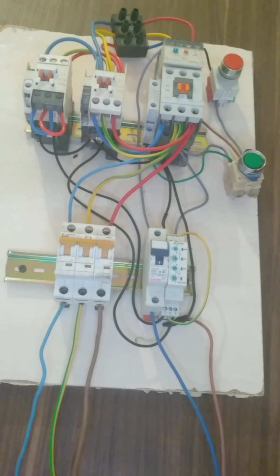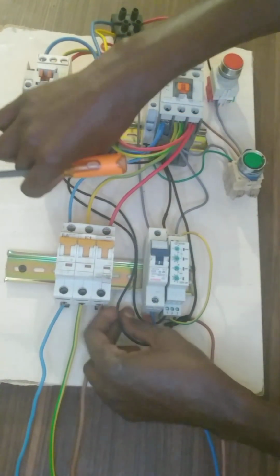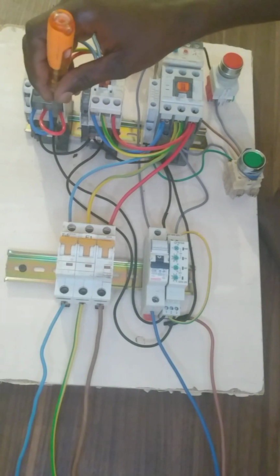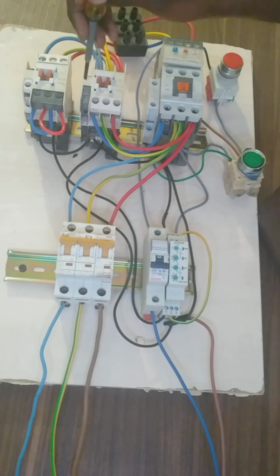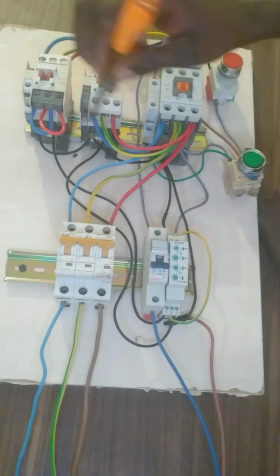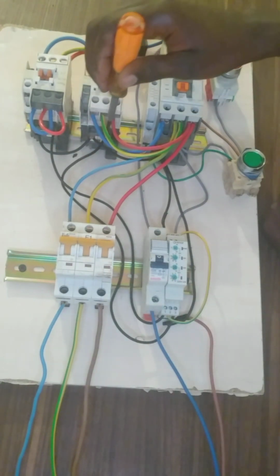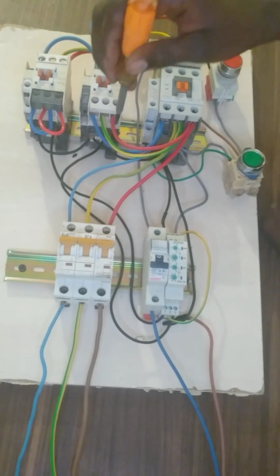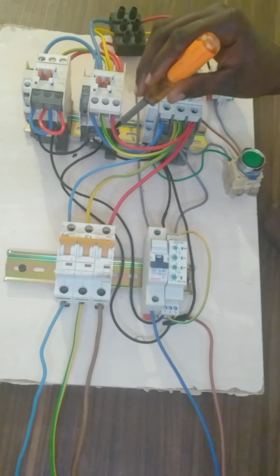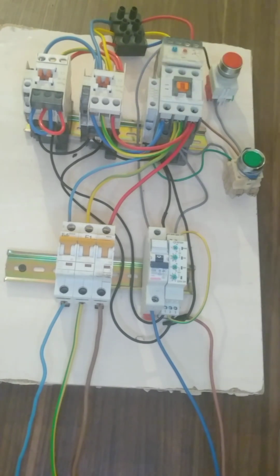Okay, there is an important thing we want to do. We want to do the electrical interlock. So number 1, which is going to the A2 of the star contactor, before it goes to this A2, I connect to the normally closed contact of the delta contactor and then return back to the A2. Also the line coming as number 3, going to the A1 of delta, I take to the normally closed contact and return back to the A2, to make the electrical interlock and protect your circuit.